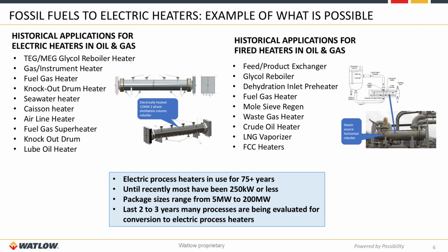I'll now talk about some of the historical applications for electric heaters and fired heaters in the oil and gas industry. On the left side, as far as electric goes, some of the common applications are glycol reboilers, gas instrument and fuel gas heaters, seawater and lube oil heaters. You'll note a picture of an electrically heated 12 megawatt two-phase column reboiler on the left side. As for the gas-fired solutions, feed and product exchangers, dehydrators, LNG vaporizers, and FCC heaters. And of note, here is a picture of a steam source horizontal reboiler.